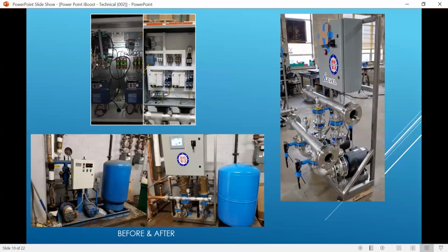And rule of thumb, you always want to read where the tank is. So if the tank is at the pump station, we're going to read from the pump station. If the tank is on the roof, we want to actually have a transducer and a reading there. We have it built into our program. We can fix an issue that happens when you're reading at a pump station and have a tank on top, because at that point you're fighting gravity and the tank. The pump's trying to push, but gravity and the tank are pushing against that, so you tend to get fluctuations, which we can fix. But the general rule is you always want to read wherever the tank is.